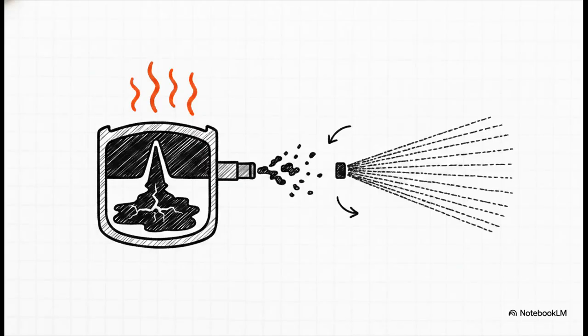So once it's safely spinning, we bring in the fuel. Now this package handles natural gas or liquid fuel, but if you're running on liquid fuel, you have got to watch out for what's called the coking trap during your shutdown. If you hit stop and don't confirm that the liquid fuel manifold fully drained out, that leftover fuel just sits there in the hot nozzles. The residual heat literally bakes it into hard carbon. That's the coking process. And that baked carbon ruins your spray pattern for the next start, turning a perfectly normal shutdown into a multi-thousand-dollar nozzle replacement job.